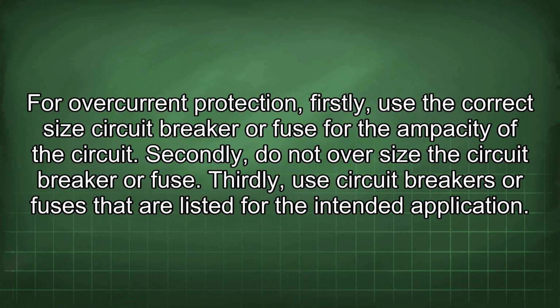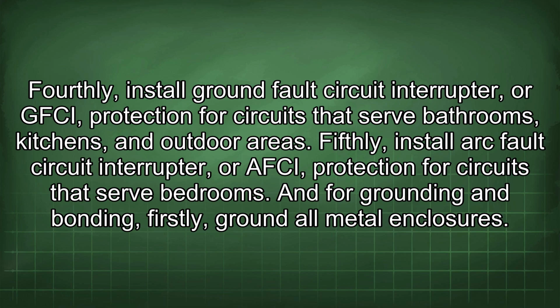For overcurrent protection, firstly, use the correct size circuit breaker or fuse for the ampacity of the circuit. Secondly, do not oversize the circuit breaker or fuse. Thirdly, use circuit breakers or fuses that are listed for the intended application. Fourthly, install ground fault circuit interrupter, or GFCI, protection for circuits that serve bathrooms, kitchens, and outdoor areas. Fifthly, install arc fault circuit interrupter, or AFCI, protection for circuits that serve bedrooms.